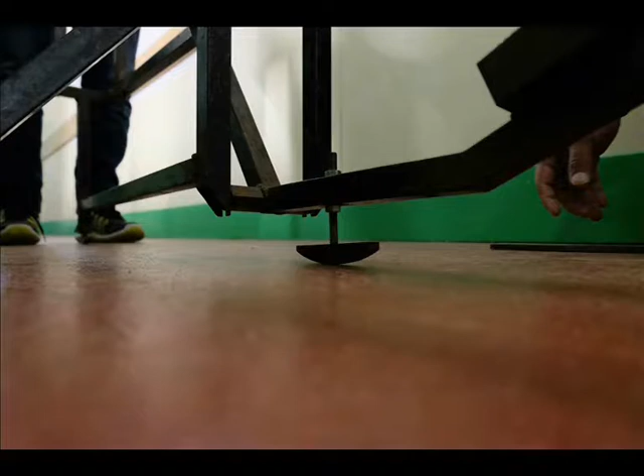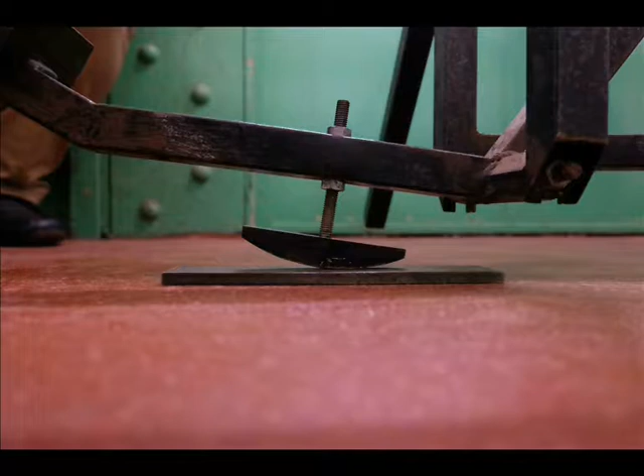The second step calibrates the measurements based upon the deviation of a known defect depth. The Merlin is rested with the probe on a smooth surface and the position of the pointer on the chart is carefully marked. The probe is raised and a metal calibration block of known dimension is placed under the probe and the new position of the pointer is marked. The process should be repeated to check that the values are consistent. The measurements made on the chart should then be multiplied by this scaling factor.